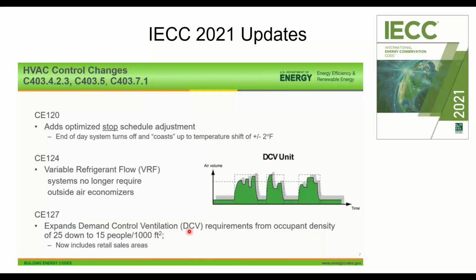It used to be 40, now it's 25, and it'll be going down to 15 people per 1,000 square foot. So if you have that ratio, 15 people per 1,000 square foot, then you'll be required to do demand control ventilation, which usually means CO2 sensors. That's the dominant way that we would do that normally. So that requirement will get stricter. So instead of it just being like conference rooms, it'll also include like some office areas and stuff like that, where you have a lot of people like sitting in cubicles near each other.